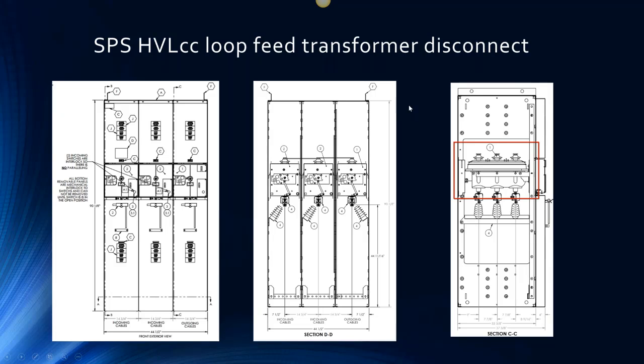So here's the switch that I'm talking about. This is a mechanism that we purchased from Schneider. It's called the HVLCC. And what you're looking at in this slide is a configuration of three pole switches. And maybe some of you are asking, why do I need 3 switches for a transformer? Well, if you have a loop system, you always want to be able to have an open point in that loop. So one of those switches is going to need to be open. And if you, for any reason, need to change the open point because of a fault, you want to be able to open and close those switches.